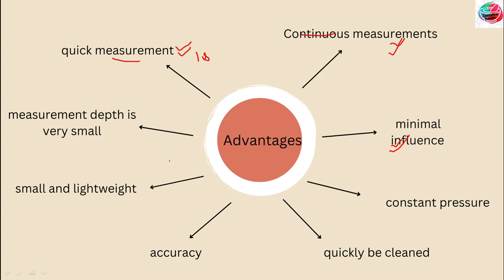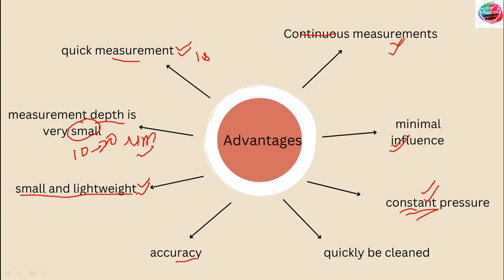The actual hydration level of the skin can be determined by this instrument. The measurement depth is very small — 10 to 20 microns of the stratum corneum — to exclude the influence of deeper skin layers such as blood vessels from the hydration level measurement. The probe is small and lightweight for easy handling and measurement on all body sites, including the lips. The spring in the probe head ensures constant pressure on the skin, enabling exact and reproducible measurements.